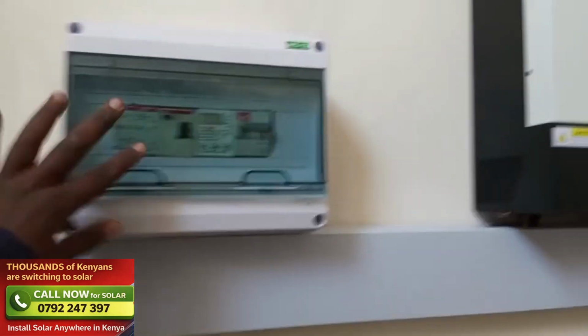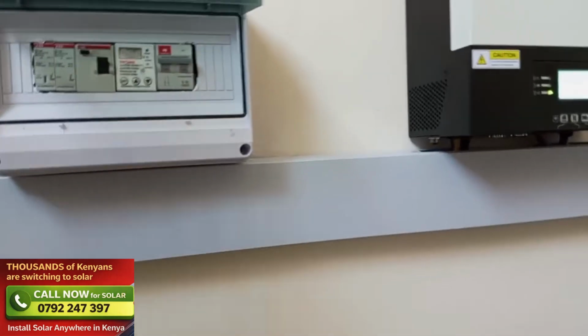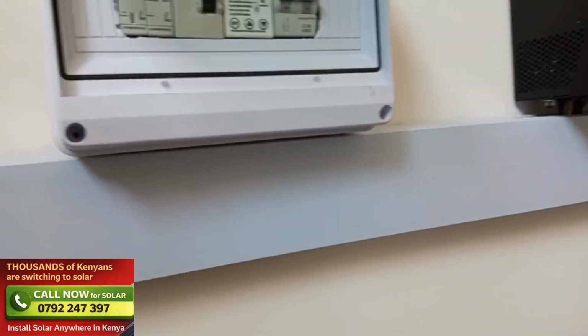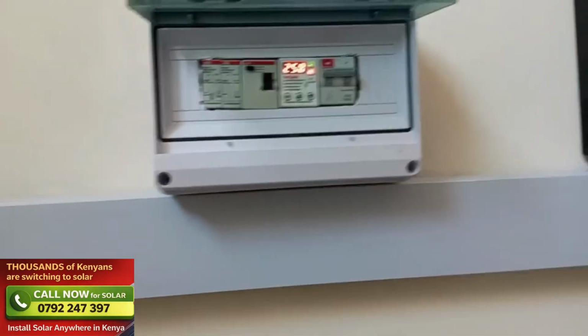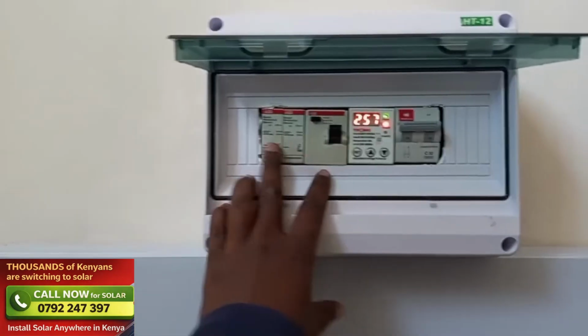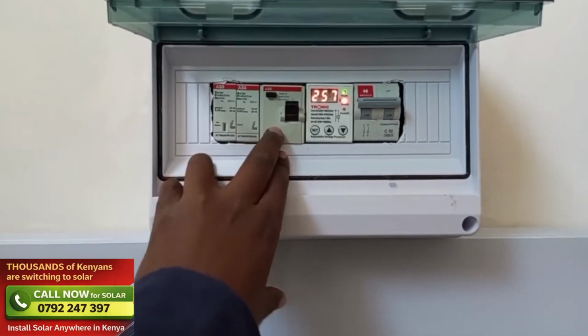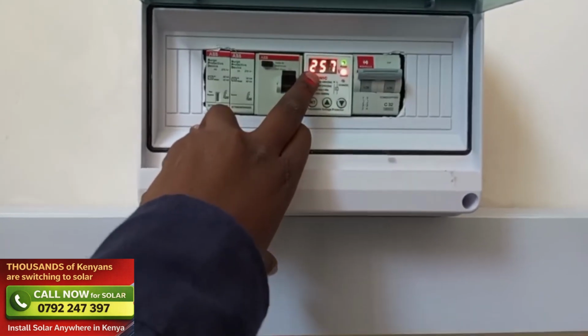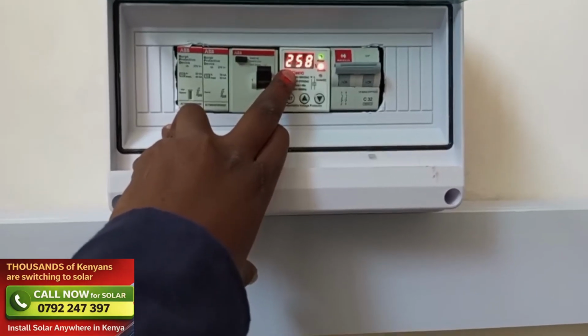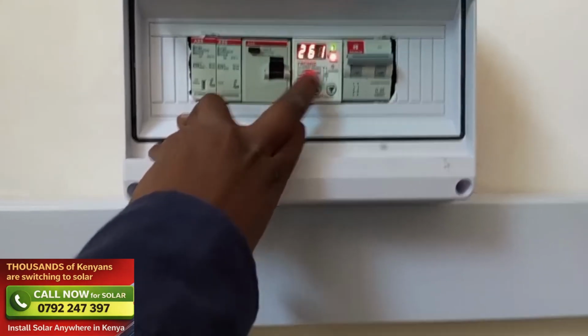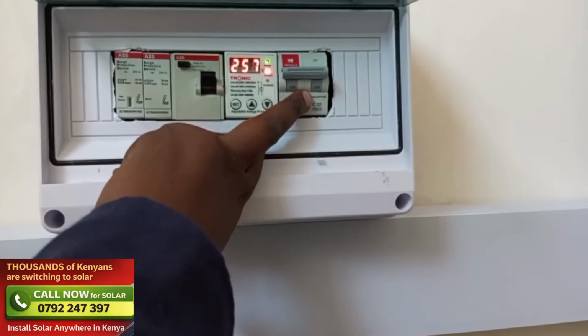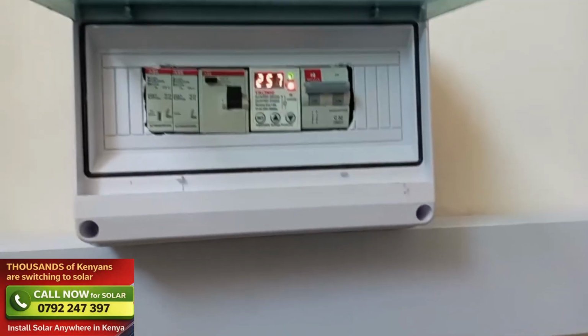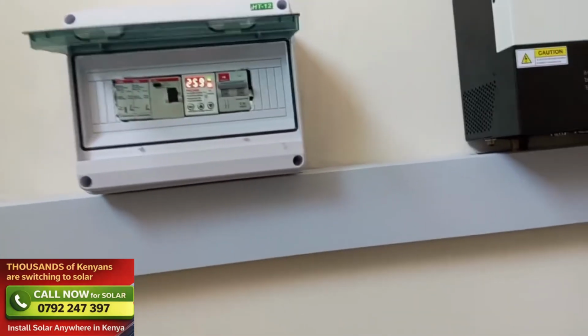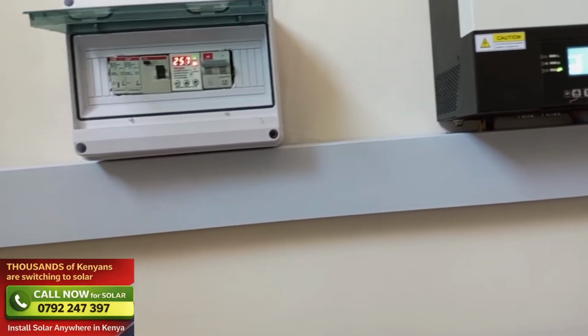As you can see here, we don't have panels charging the batteries. We have connected the SPD, RCDs, and the voltage regulator, which shows that the voltage of the supply to the university is quite high. We also have a DC breaker and an AC breaker, to ensure that whatever is fed to the inverter is within the right limit.